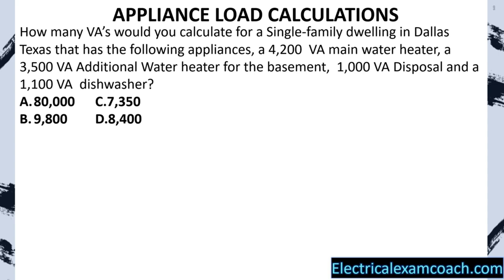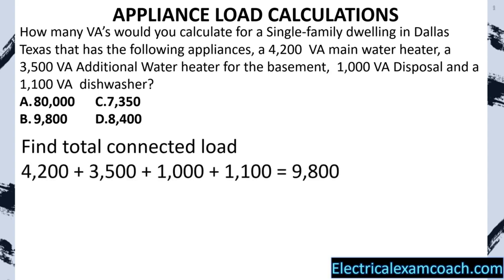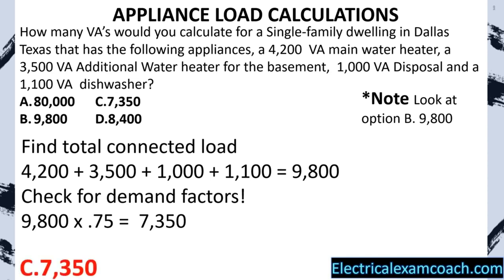Practice problem: How many VAs would you calculate for a single-family dwelling in Dallas, Texas with a 4,200 VA main water heater, a 3,500 VA additional water heater for the basement, a 1,000 VA disposal, and a 1,100 VA dishwasher? Find total connected load: totaling it up equals 9,800. Check for demand factors — sure enough, we have four or more fixed appliances, so we apply the 75% rule. We take 9,800 multiplied by 0.75, giving a new reduced load of 7,350 VAs. Note that option B was 9,800 as if you didn't apply the 75% rule — you've got to be careful. We select C.